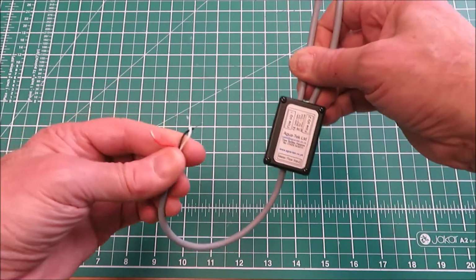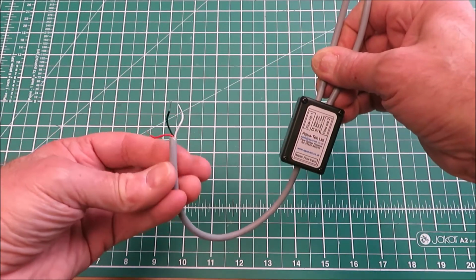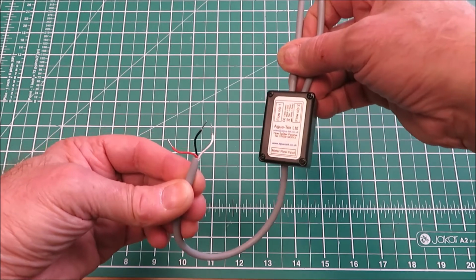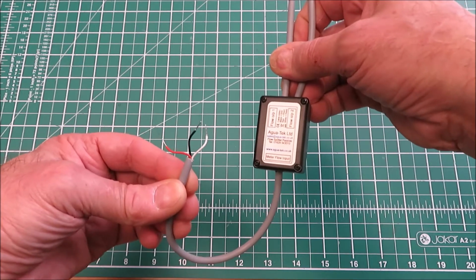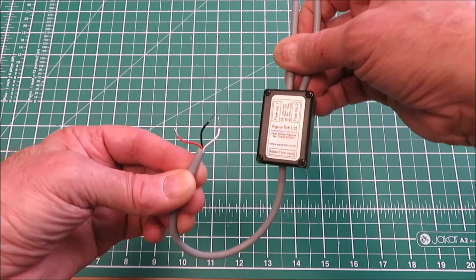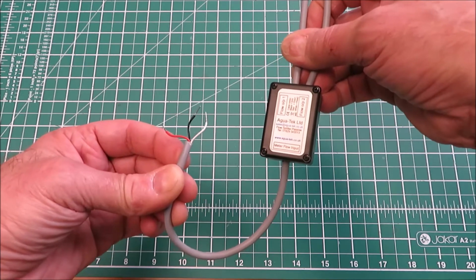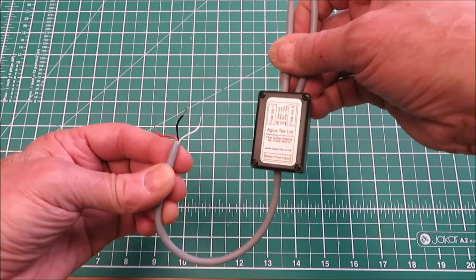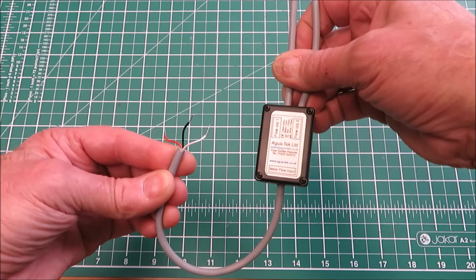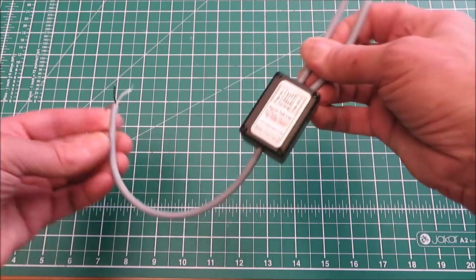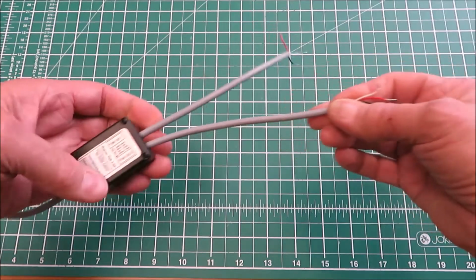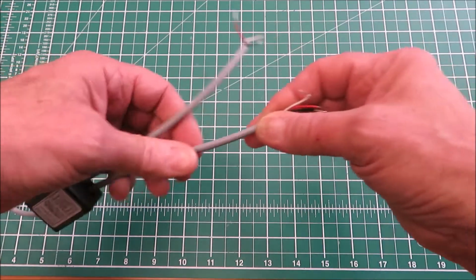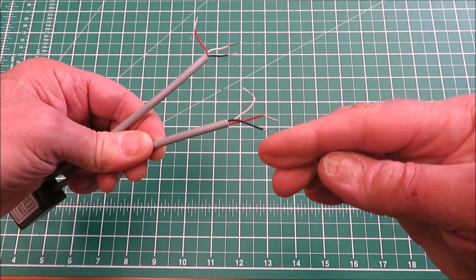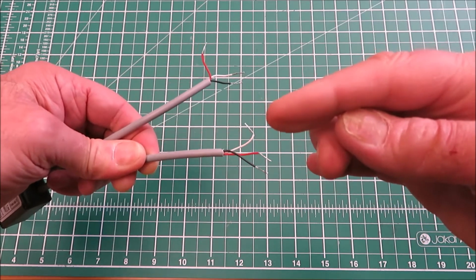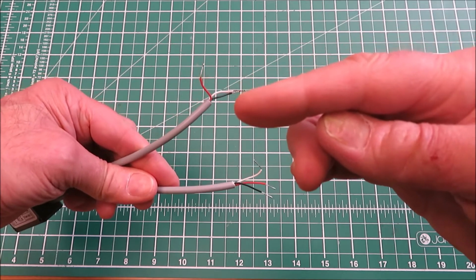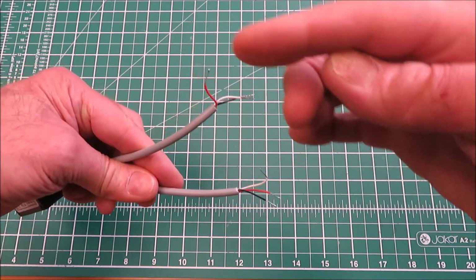You can see that when the cable is bared back, the input has a black, common or ground wire, a white wire and a red wire. We generally call the red wire flow input 1 and the white wire flow input 2, but actually they're not particularly numbered. They're just 2 separate flow channels, and these come out of the splitter on 2 separate cables, again with a black wire which is common and ground, the red flow and the white flow, and the same on the other output: ground, flow on the white and flow on the red.